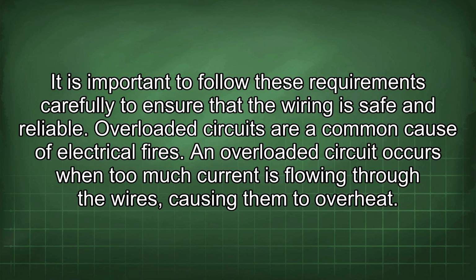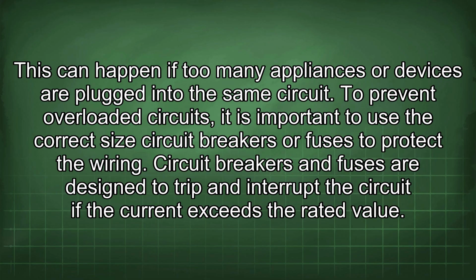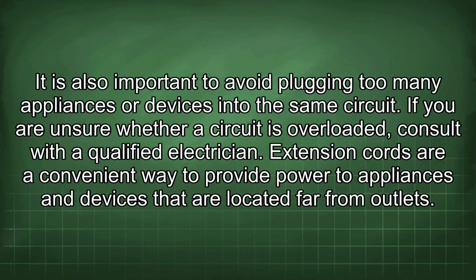Overloaded circuits are a common cause of electrical fires. An overloaded circuit occurs when too much current is flowing through the wires, causing them to overheat. This can happen if too many appliances or devices are plugged into the same circuit. To prevent overloaded circuits, it is important to use the correct size circuit breakers or fuses to protect the wiring. Circuit breakers and fuses are designed to trip and interrupt the circuit if the current exceeds the rated value. It is also important to avoid plugging too many appliances or devices into the same circuit. If you are unsure whether a circuit is overloaded, consult with a qualified electrician.